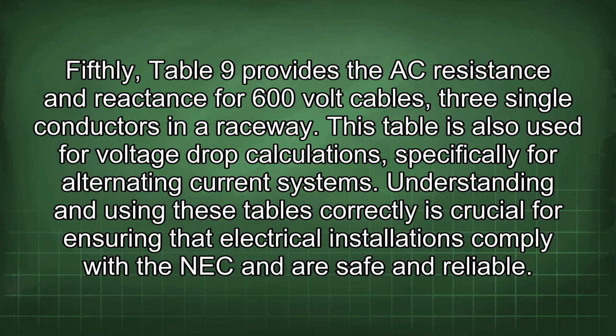Fifthly, Table 9 provides the AC resistance and reactance for 600-volt cables, 3 single conductors in a raceway. This table is also used for voltage drop calculations, specifically for alternating current systems.